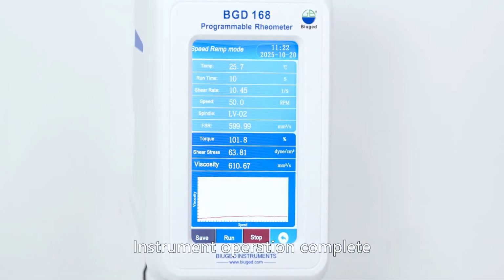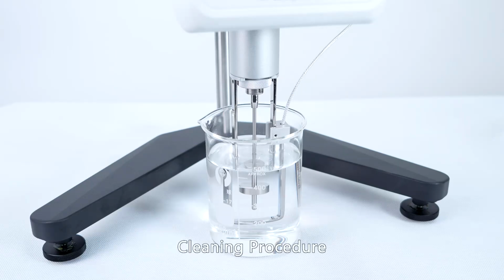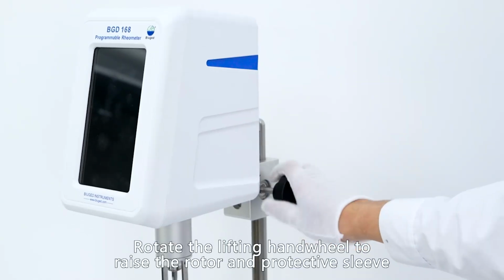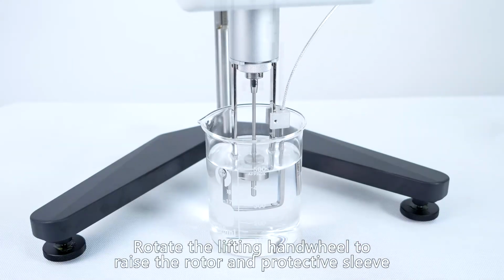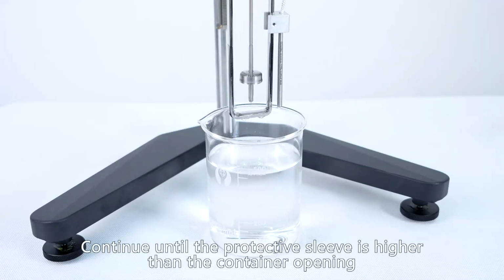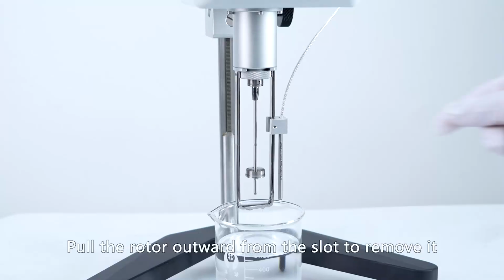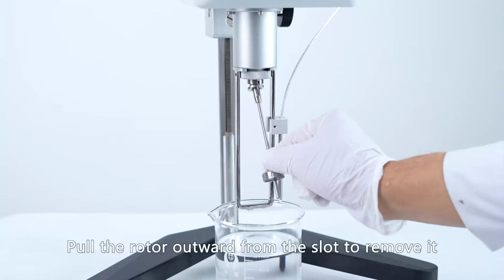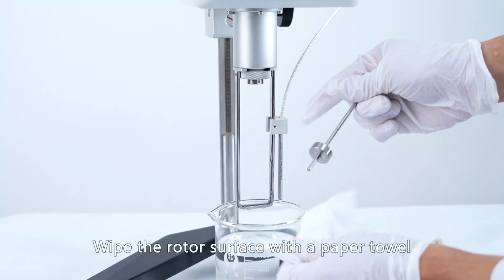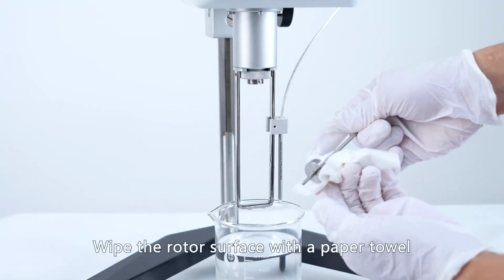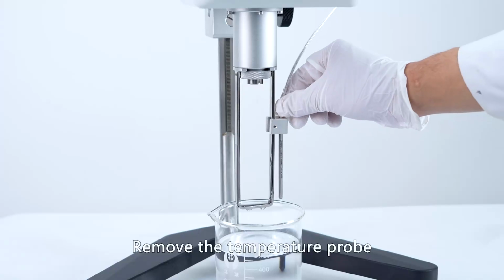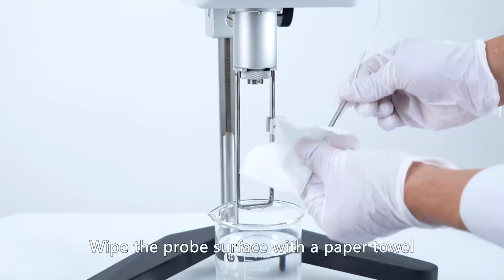Instrument operation complete. Cleaning procedure. Rotate the lifting handwheel to raise the rotor and protective sleeve. Continue until the protective sleeve is higher than the container opening. Pull the rotor outward from the slot to remove it. Wipe the rotor surface with a paper towel. Remove the temperature probe. Wipe the probe surface with a paper towel.